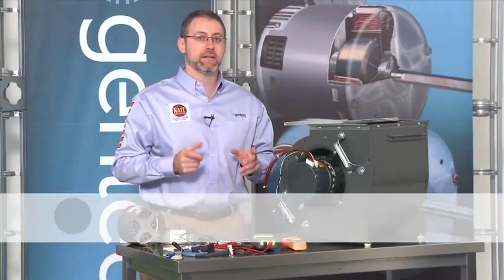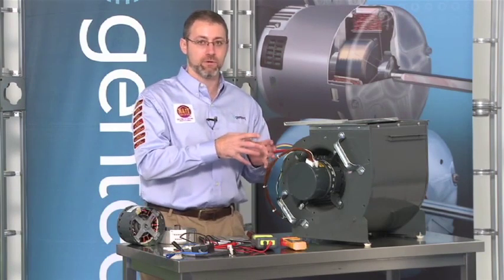So to recap where we are, we've diagnosed that the motor does not run with the TecMate. We've already confirmed that we had high voltage power to the high voltage connector. So now we need to remove the control and diagnose whether the motor is also failed.